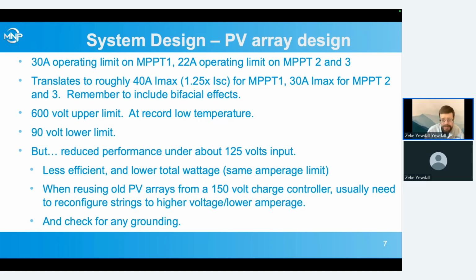Remember to include bifacial effects when you're thinking about this. If you're doing bifacial ground mounted arrays, they could be somewhere in the 10 to 25% higher current than the normal STC rating. We don't want to exceed this current because that's going to cause damage to the inverter.